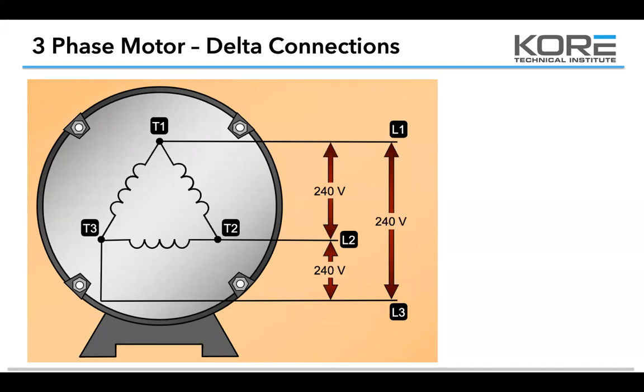You need to check all three of your combinations anytime you're dealing with a three-phase troubleshooting application, because it's going to tell you certain things. Usually on these motors, if you're throwing an amp clamp around the leads when the motor's running, you should get common amps across a three-phase motor. So if you're pulling 3.2 amps on L1, you should pull 3.2 on L2 and 3.2 on L3. It should be really close. That's how you know you're doing fine.